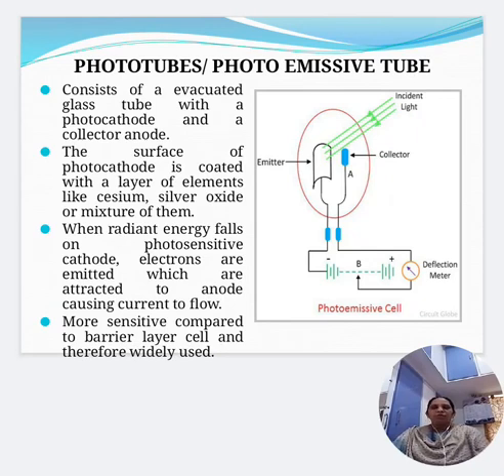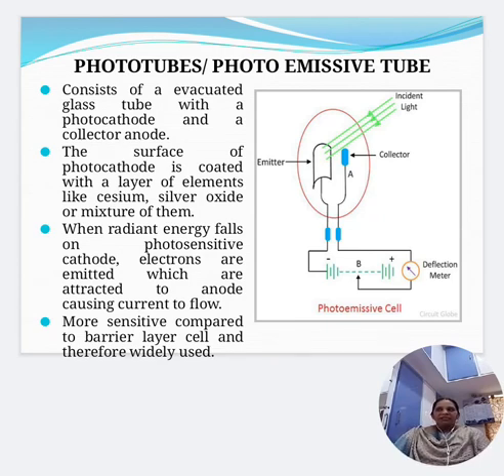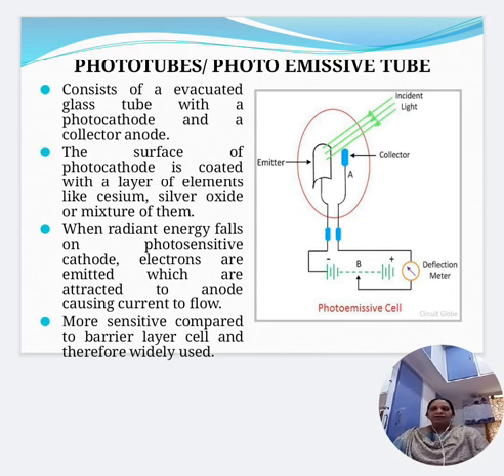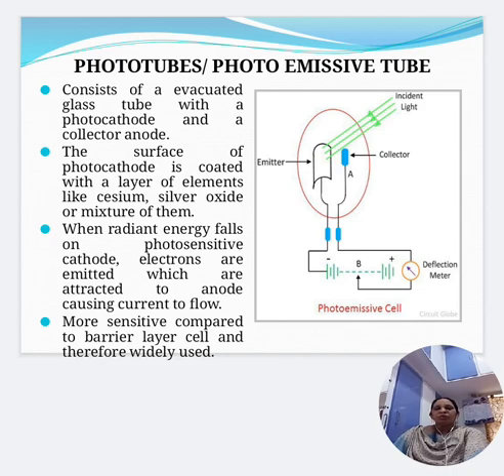Photo tubes or photoemissive tubes consist of an evacuated glass tube with a photocathode made of a light-sensitive material and a collector anode. The surface of the photocathode is coated with cesium, silver oxide, or a mixture of them. When radiant energy falls on the photosensitive cathode, electrons are emitted and attracted towards the anode, causing current to flow through the external circuit. Photo tubes are more sensitive compared to barrier layer cells and are therefore widely used.